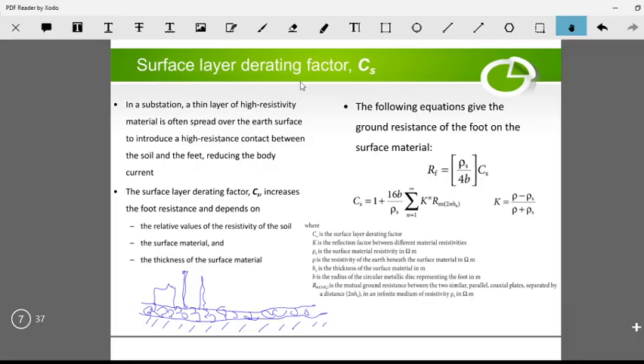This layer acts as a derating layer. It's a high resistivity material spread throughout the earth surface in the substation, which reduces the current flowing through the body if a touch potential or step potential happens, because the resistance of this layer is high compared to the ground, creating a high resistive path to the ground.